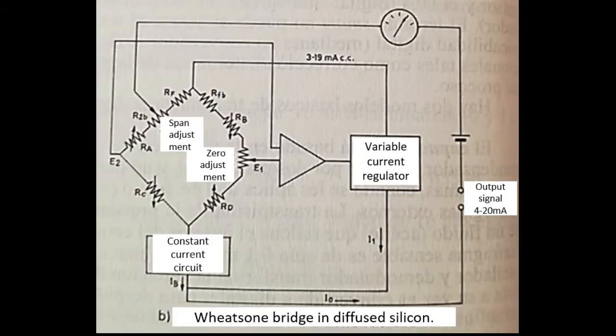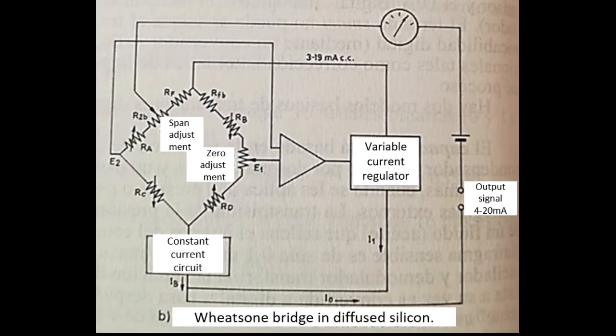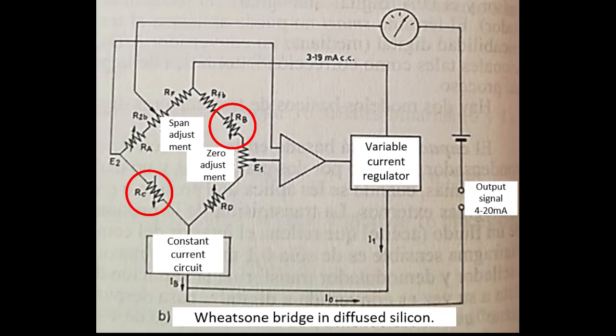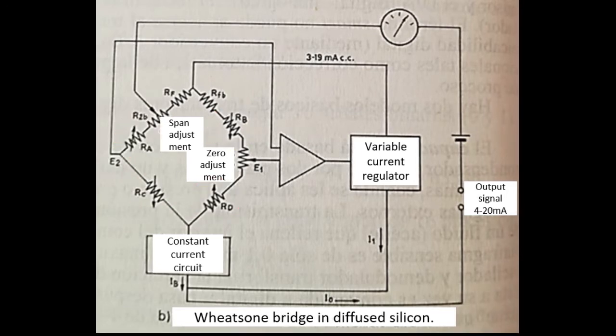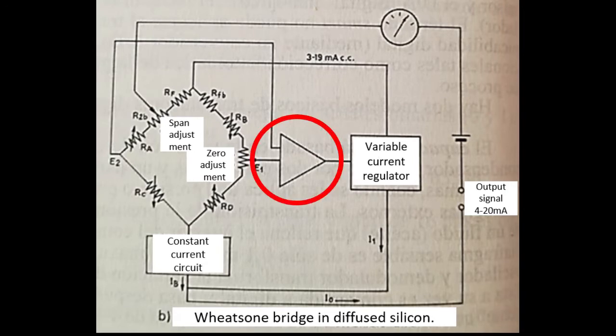This behaves like a dynamic Wheatstone bridge circuit. E1 and E2 are equal when there is no pressure. When pressure is applied, Rb and Rc decrease their resistance while Ra and Rd increase it, which causes voltage drops and a difference between E1 and E2. This is applied to a high-gain amplifier that controls a variable current regulator.